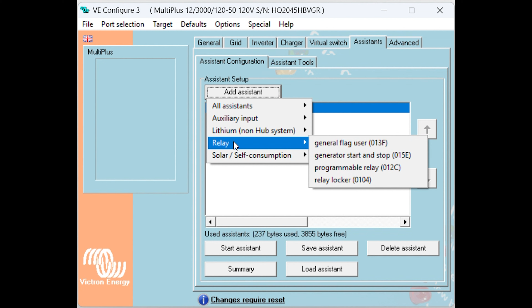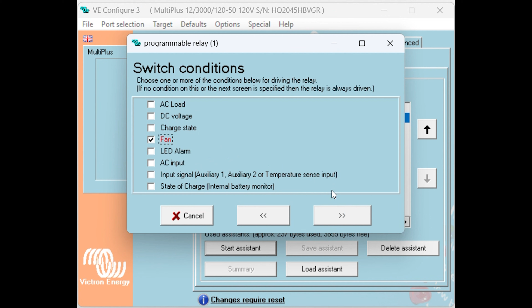Now we have to turn the fans off, so we add another assistant for that—again programmable relay, select K1, again the MultiPlus fan. So when the fan is off for 30 seconds, the relay closes and takes the power away from the computer fans. That's it.